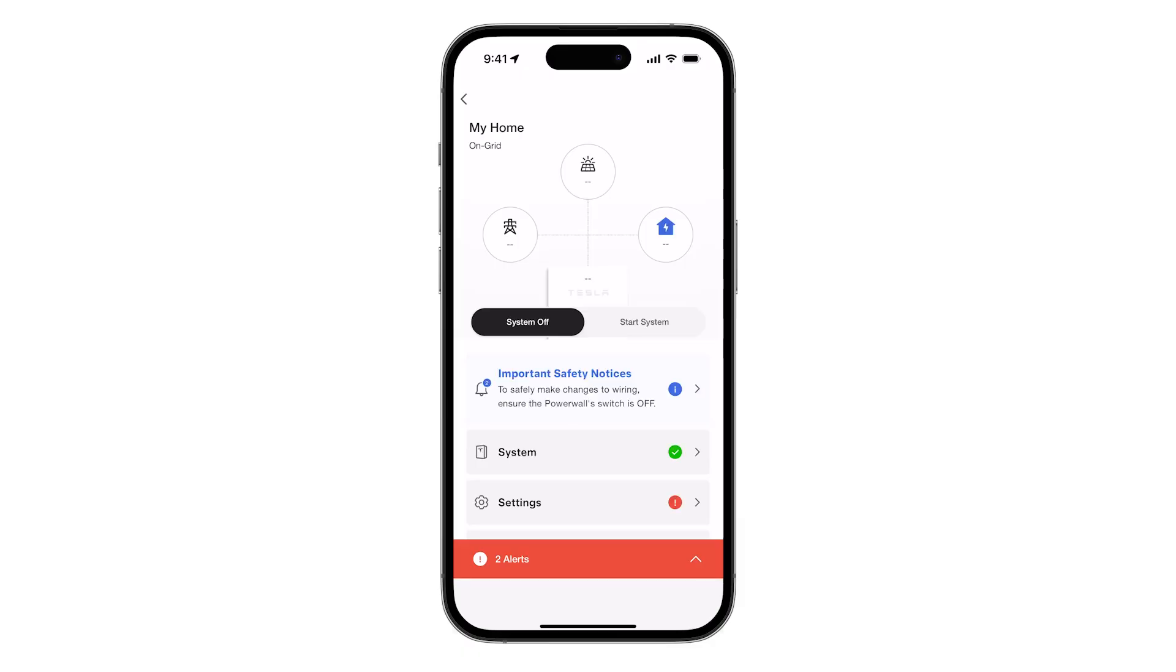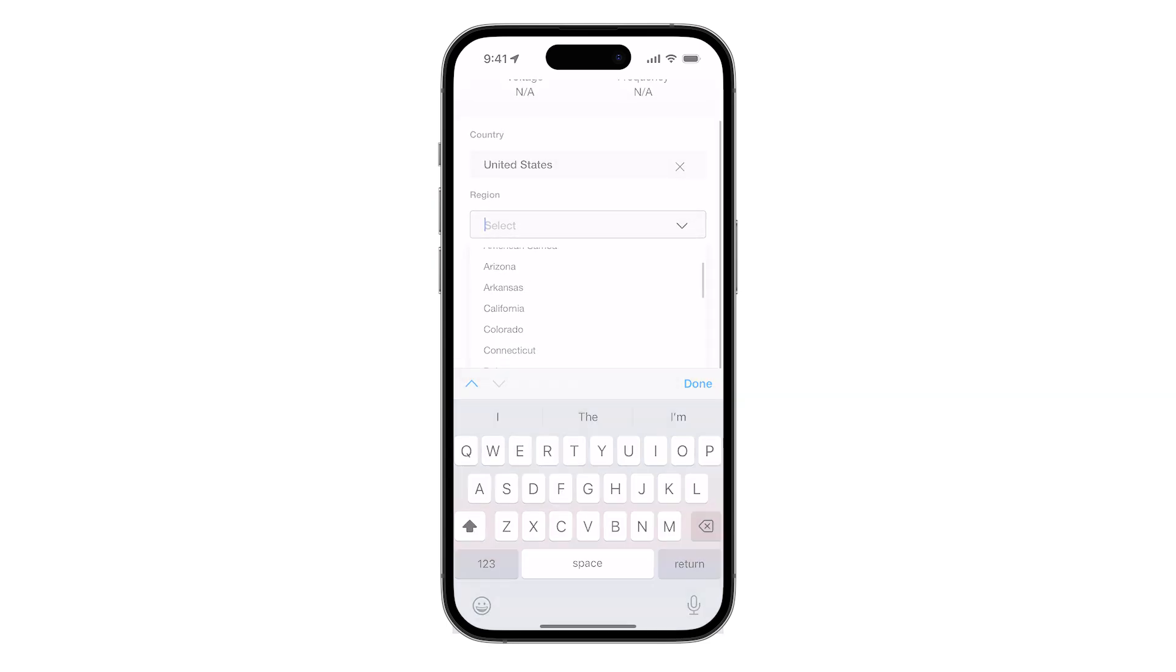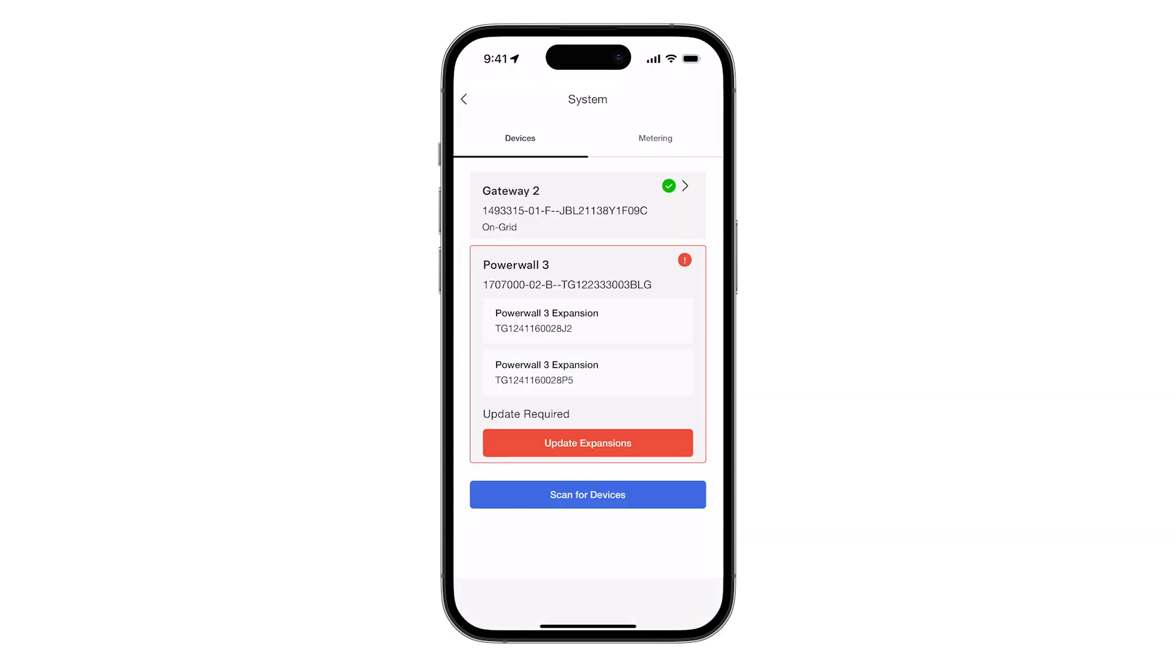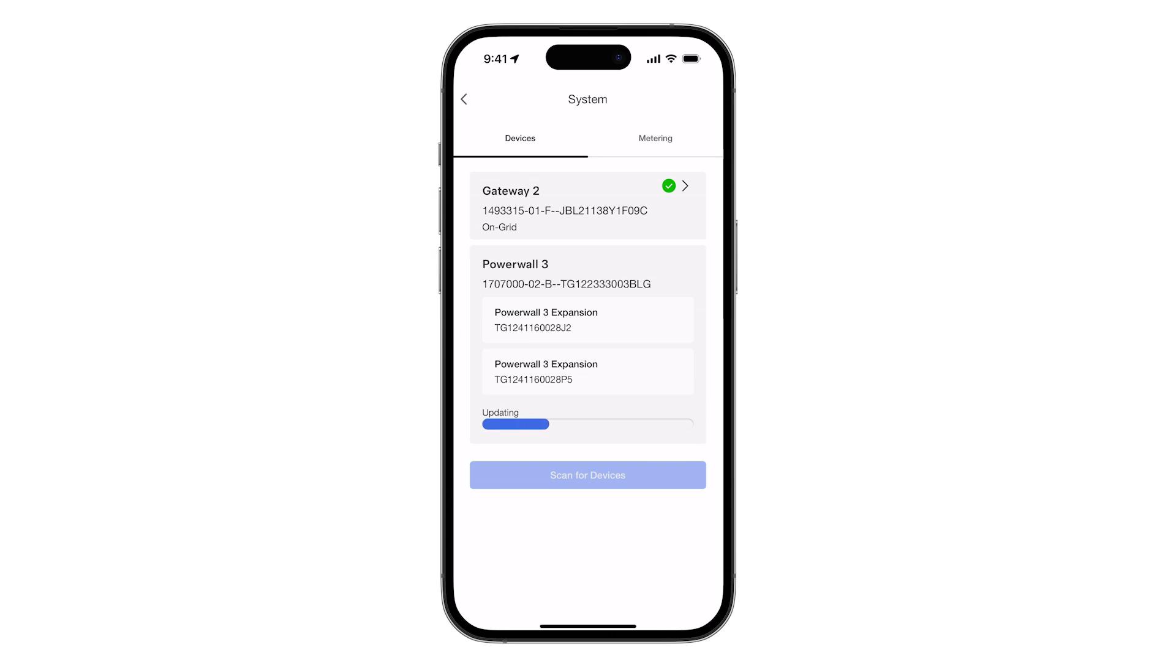Proceed with the standard commissioning procedure performed through the Leader Powerwall 3. On the Devices page, verify that all Powerwall expansion units are detected and present in this list. If an update is available, tap Update Expansion and wait for it to complete.